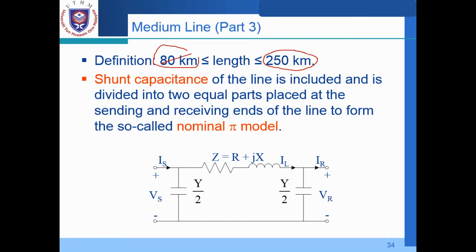And it is covered from 80 kilometer and then up to 250 kilometer. So we do have the shunt capacitance, which has been neglected in the short line model. But taken into consideration this time around, included and divided into two equal parts placed at the both sending and receiving ends of the line to form the so-called nominal π model. So this is the representation part of the medium transmission line.